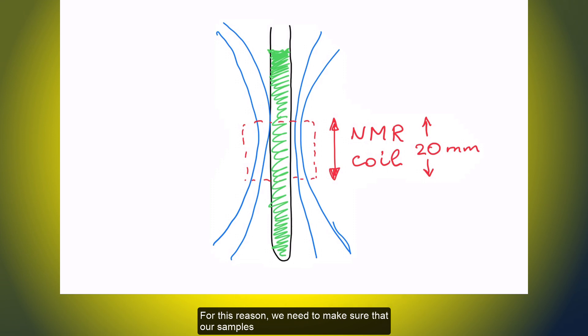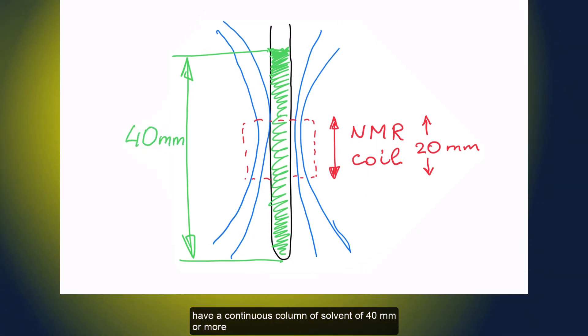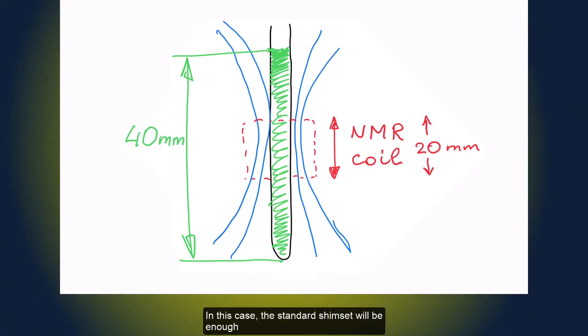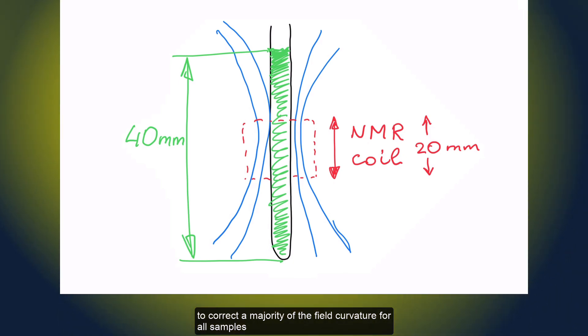For this reason, we need to make sure that our samples have a continuous column of solvent of 40 mm or more. In this case, the standard shim set will be enough to correct a majority of the field curvature for all samples.